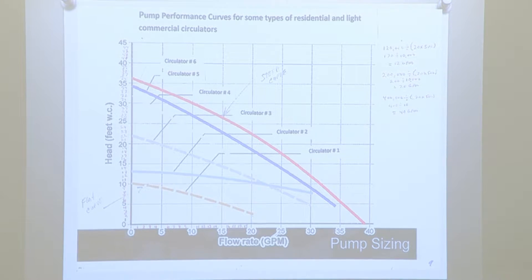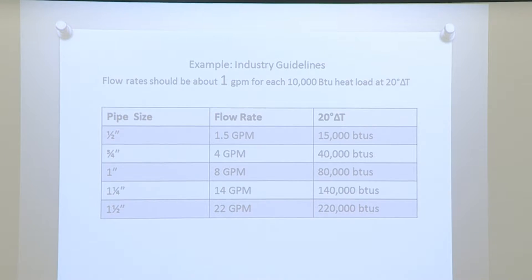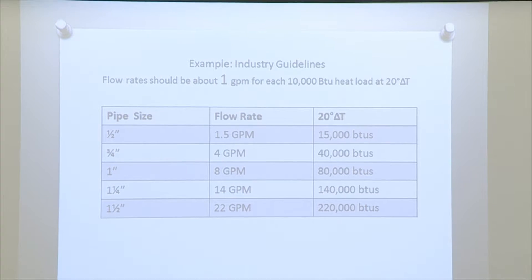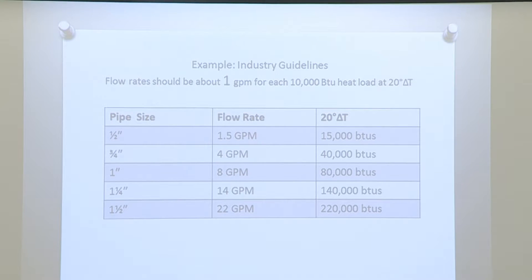Here's the pump performance curve. With a flow rate of 9 GPMs and a head of 5.4 feet, circulator number one could handle this system. Here are some industry guidelines: the flow rate should be about 1 gallon per minute for each 10,000 BTU at a 20 degree delta T. The chart gives you flow rates and pipe sizes based on 20 degree delta T, though different delta T's exist.